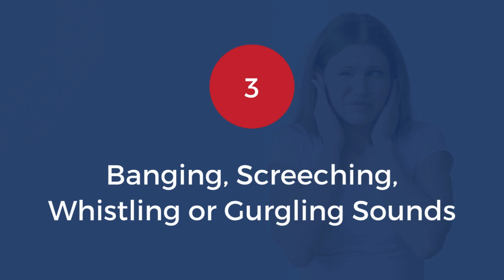3. Banging, screeching, whistling or gurgling sounds. Air in the system is the most common reason for this noise. But these sounds may also be a sign of impending pump failure, or early symptoms of a kettling problem that will only get worse with time. If these noises are persistent, you might try bleeding your radiator. This is a simple procedure that can remove any excess air from the pipes. If kettling is suspected, you can have a professional perform a power flush. Should the strange noises continue, contact your HVAC contractor to arrange an inspection.